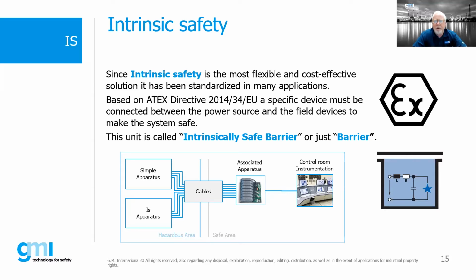But here's the important thing to remember on intrinsic safety. You really need to look at the entire loop, if you will. Because we basically take a barrier, we take our field apparatus, we take a look at the cabling, we look at our incoming power that's coming from our control room, and we look at this as a system. And so intrinsic safety is a true system concept. And it's actually one of the few, if not only, true electrical protection concepts. Almost all the other protection concepts are mechanical in nature. Intrinsic safety is actually an electrical concept. So we call these basically intrinsically safe barriers, or sometimes we call them barriers. The common terms, ISBs. And basically, it's pretty much around the world, we call them the same thing, if you will. We use the same verbiage in the United States, Canada, as we do in Europe and in the IEC world as well.